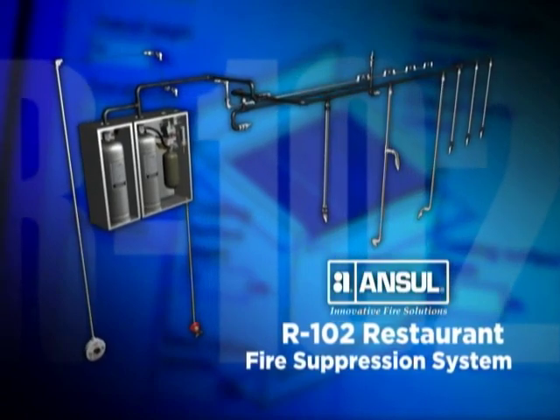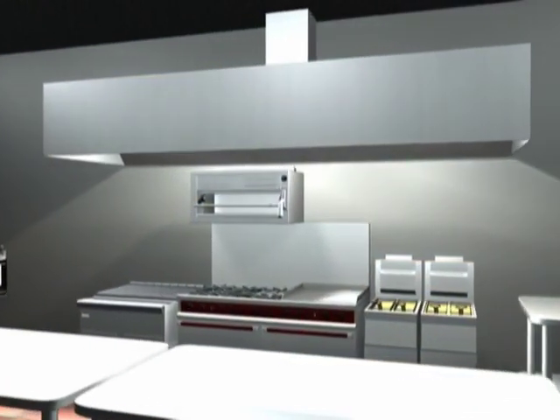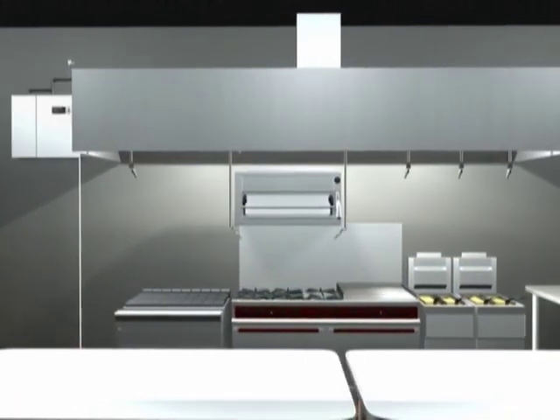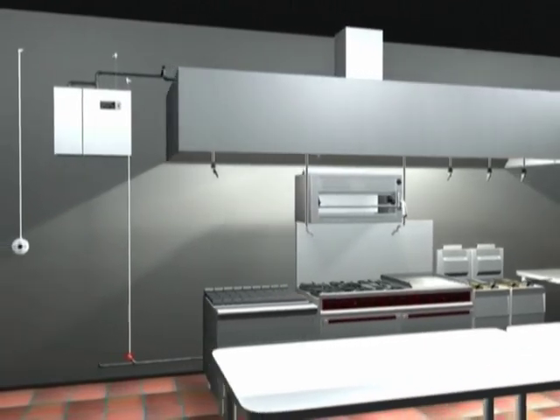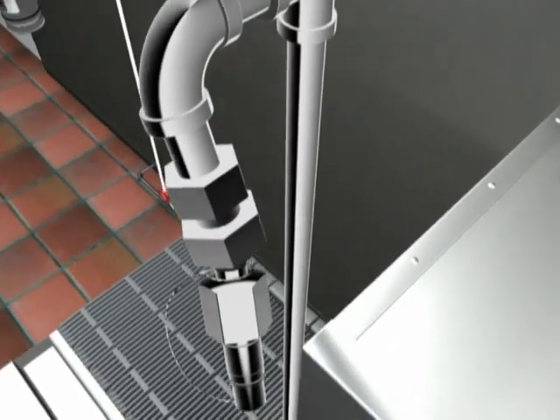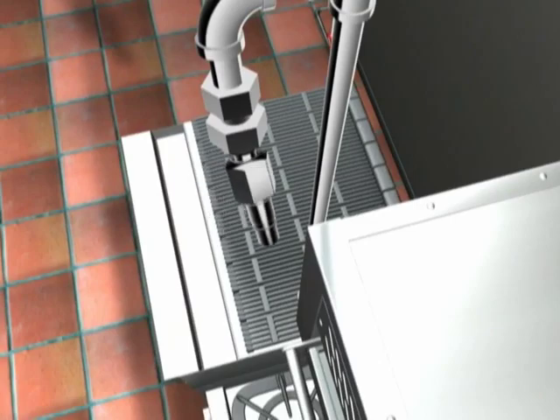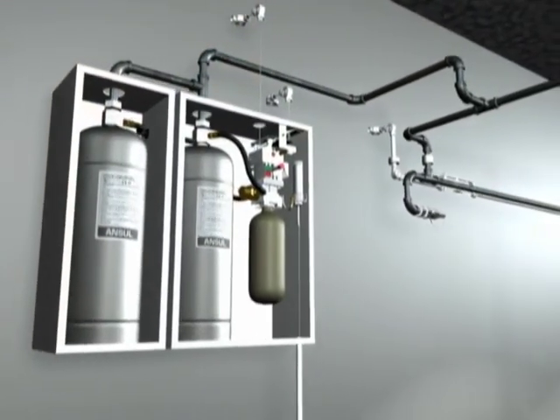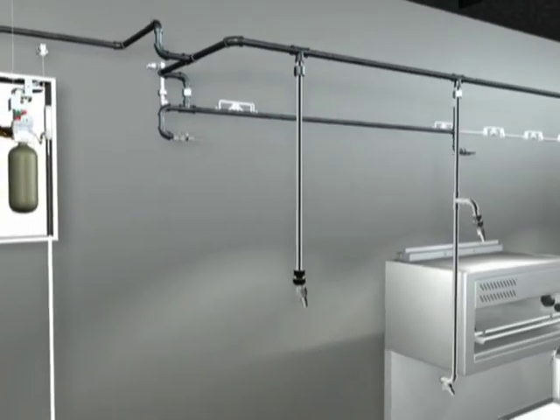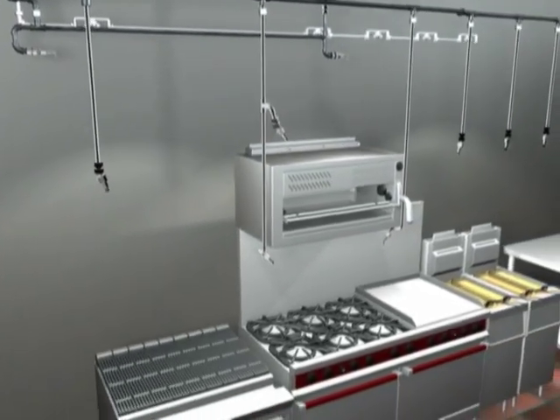The Ansul R-102 Restaurant Fire Suppression System provides you with two design options. The primary is an appliance-specific design where nozzles are aimed at specific hazard areas of the appliance. This is considered the most economical design because the agent is aimed only where it is needed.